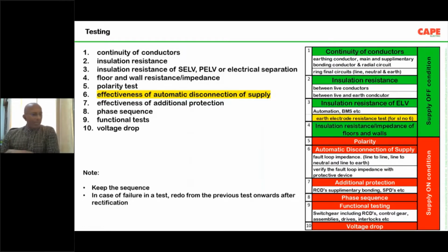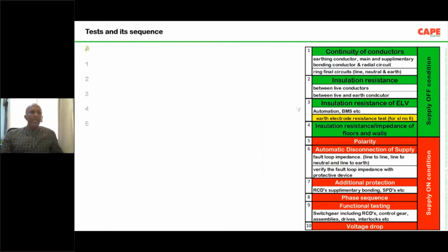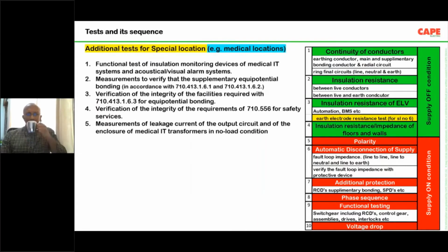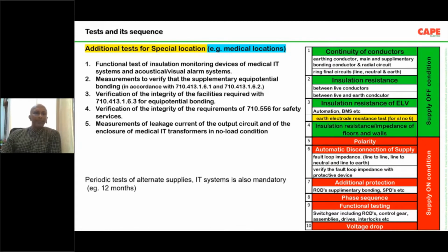Now, these 10 tests are mandatory for a normal building. There are installations which are special. Special in the sense, in the standards, these are called special locations, like a bathroom in a house, a swimming pool, maybe a car charging unit, a solar PV installation, a medical location. These special installations require special additional measures, additional testings. We will look into it in this slide later. Not only initial testing, periodic testing is also mandatory for special locations.